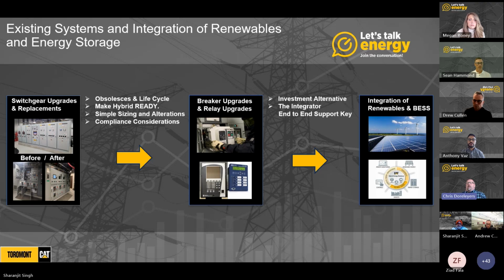And I'll go back to the integration discussion: when you're looking at potentially doing a retrofit, you want to take all those obsolete parts and consider them in conjunction with the rest of the system. Because oftentimes, if you upgrade a component in a particular section like a switchgear, there may be other downstream upgrades that need to be affected. You might be altering the communications as you do an upgrade, and now it no longer works with upstream components. So again, a system end-to-end approach is required.